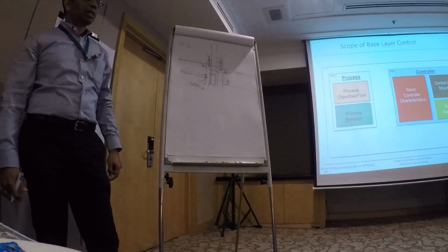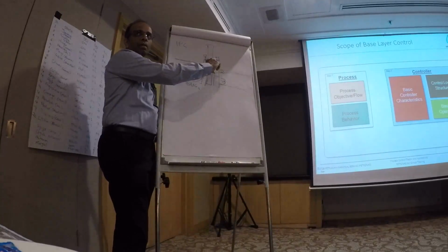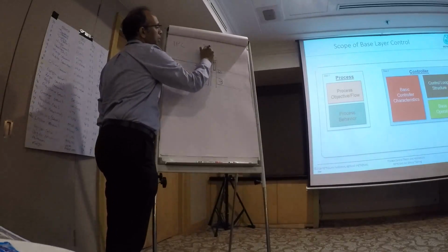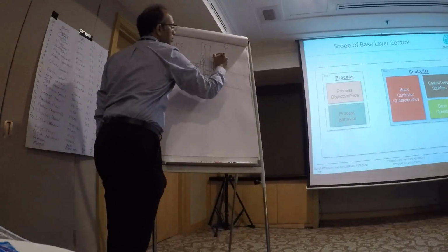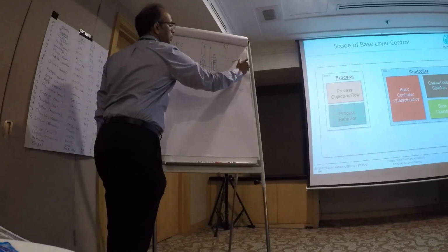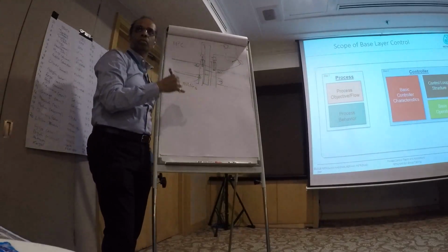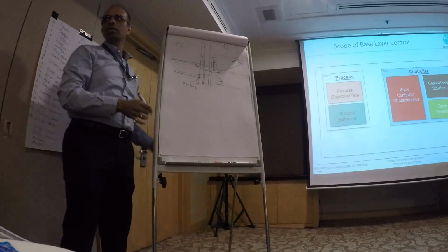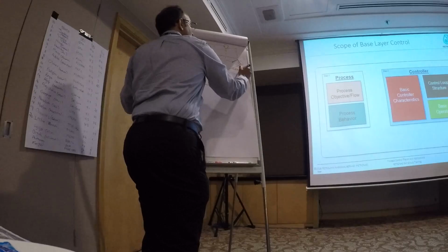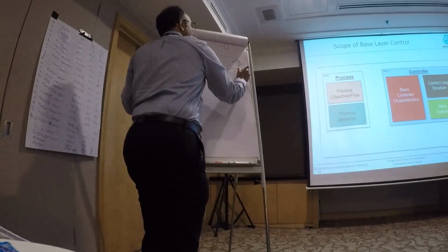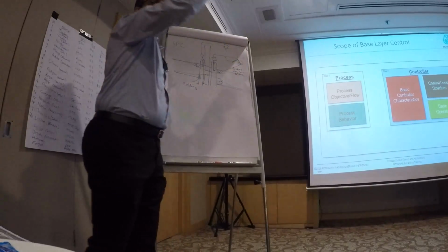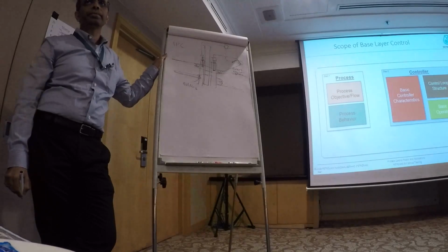Anytime you have a restriction in a pipe, you will end up with flow disturbances. When you measure this, you will start to see noise, and it is caused by that. It could be eddies, it could be cavitation, it could be flashing. All of them can cause that noise to happen.